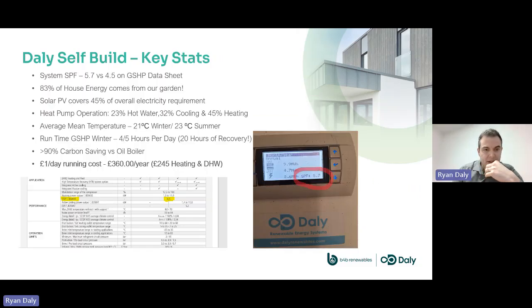And then just some of the stats coming out of that. Our SPF on our heat pump: if you look at the data sheet, it's rated 4.5, but our actual real life performance is 5.7. A lot of that is down to the fact that it's cooling as well, so we're putting that energy from the house back into the ground for 4 or 5 months of the year. Because of that SPF, 83% of our energy comes from the garden. So the heat pump compressor is only providing 17% of the energy to produce our heating, hot water and cooling.